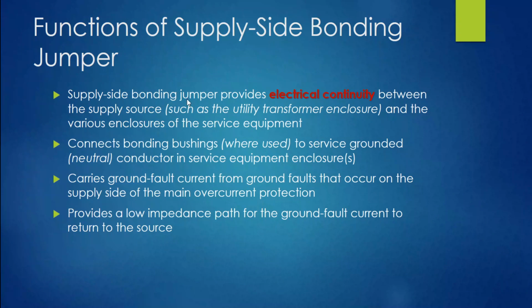Now, what are the functions of the supply side bonding jumper? Remember, the supply side bonding jumper is everything that's on the line side or the supply side, moving towards the transformer, in the opposite direction of your main disconnecting means inside of the service equipment. Okay, it is on the line side of it. The important thing to remember is there's no known overcurrent protective device on the line side. With that said, you're still required to bond all of these enclosures, raceways, meter sockets, meter enclosures, all of it together. And we'll see that in the requirements of 250.92(A).